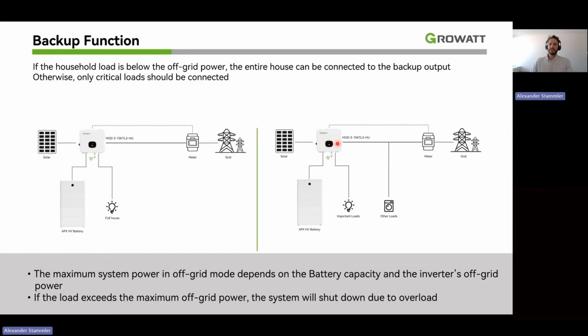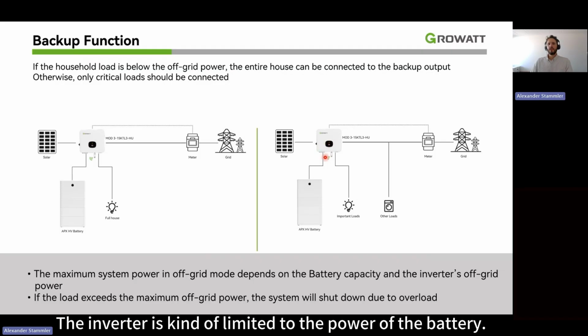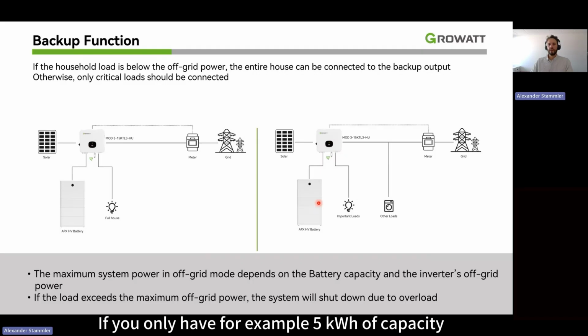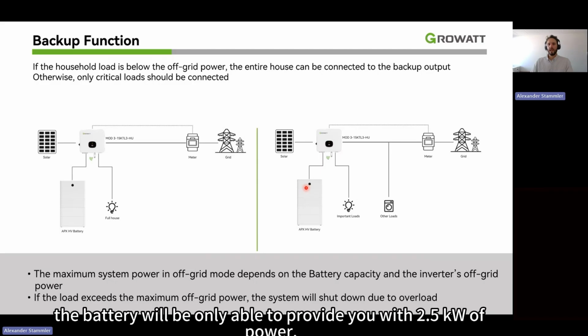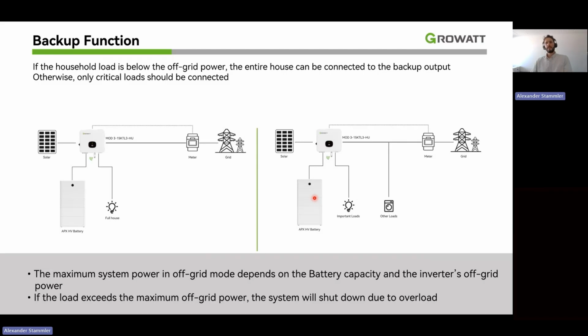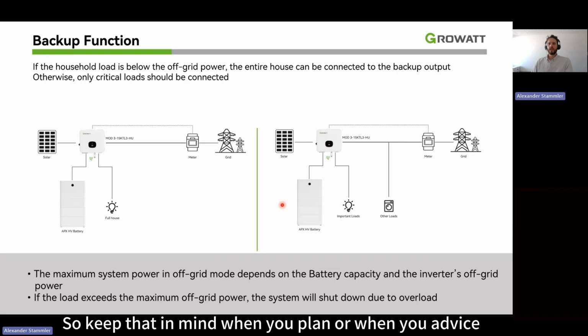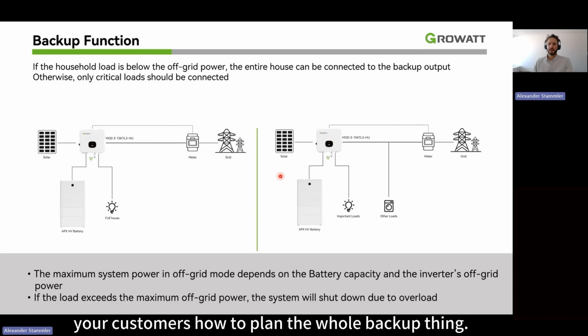Then the next problem is, as in the old one, once the grid is gone, it's a blackout. The inverter is limited to the power of the battery. If you only have, for example, 5 kilowatt hours of capacity, the battery will only be able to provide you with 2.5 kilowatts of power. So keep that in mind when you plan or when you advise your customers how to plan the whole backup.